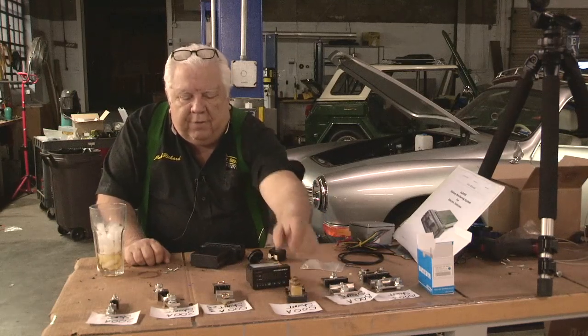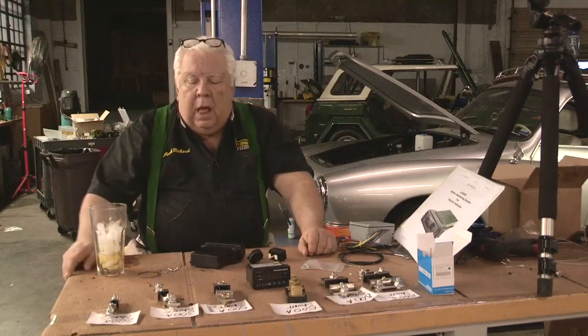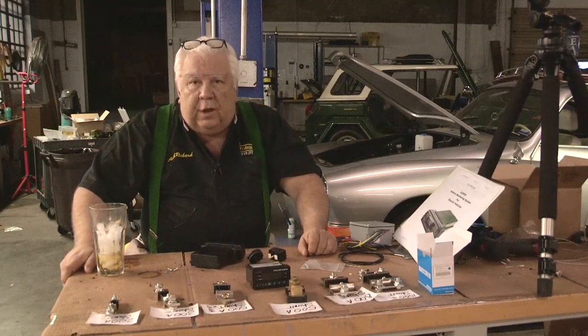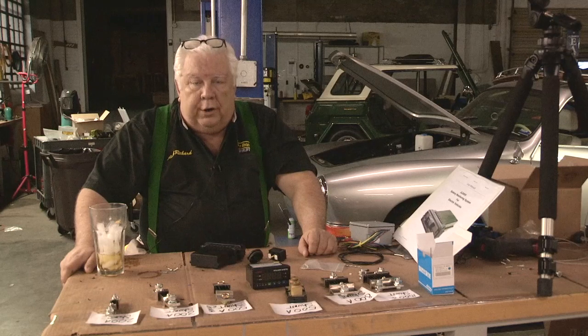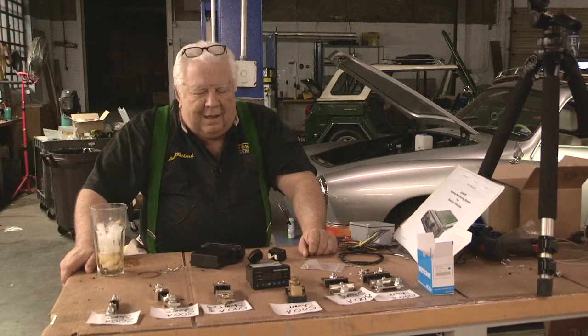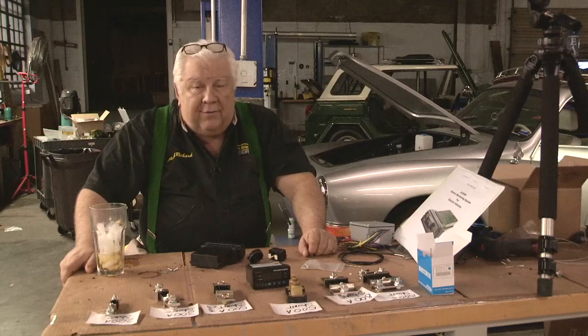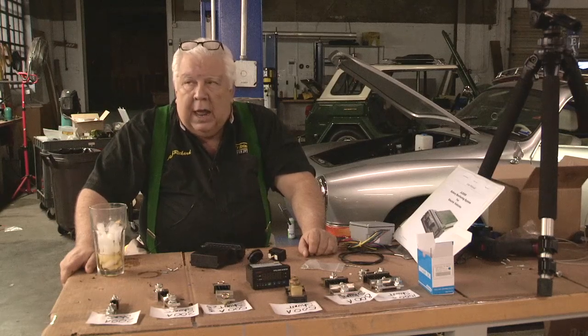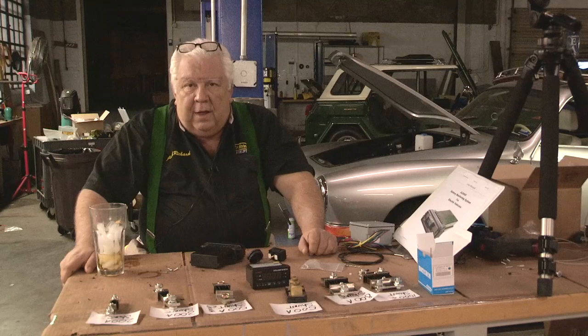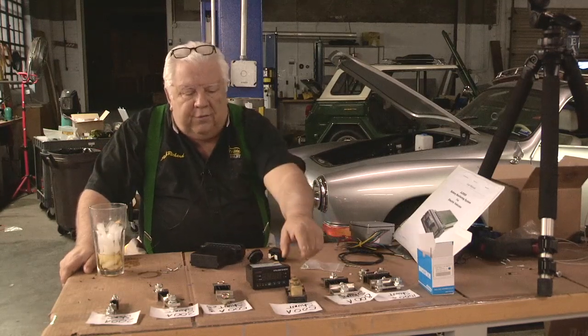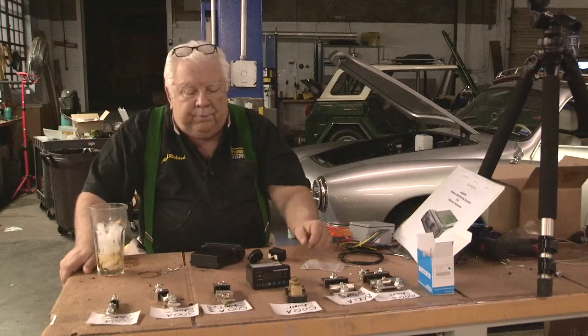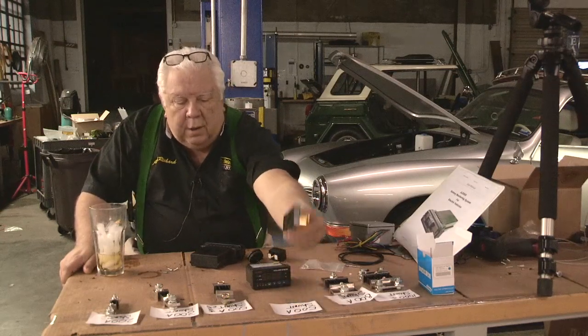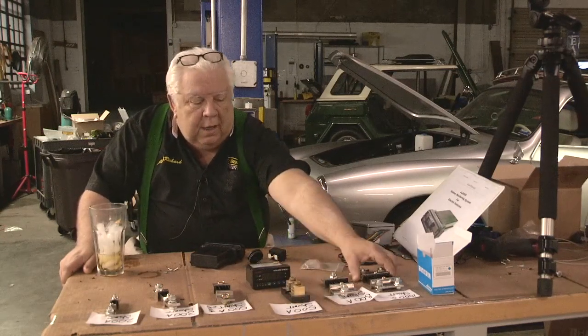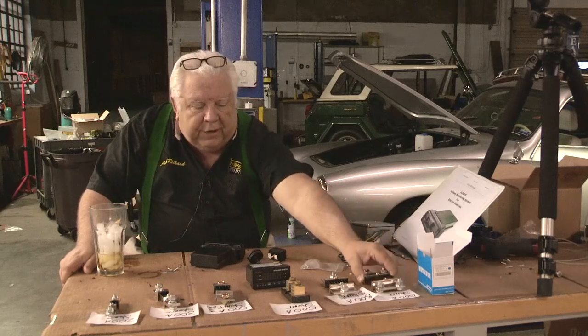A lot of you get very wrapped around an axle about having the right size shunt for the amount of current you're going to use. It's a little more complicated than that. You do want to have a shunt big enough to handle your current. Typically, it's very safe to handle 1.5 times the stated amount of current. So this 500 amp can carry 750. This 1000 amp can carry 1500 amps.